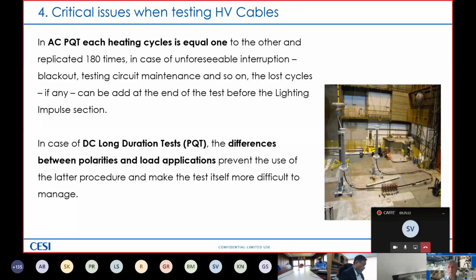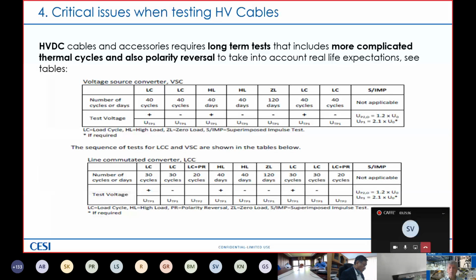Totally different situation for a long duration test in DC. Because unfortunately, here we have differences between polarities and load application. And this unfortunately prevents the use of the latter procedure, the one to put cycles at the end, and makes the test itself, of course, more difficult to manage. In fact, if you look at this taken from IEC 62895 or CIGRE Technical Brochure 490, these are the load cycling, the 180 cycles to be applied for the long duration test. In this situation, if you look at the voltage source converter or the line commutated converter, in one case, you do not reverse the current flux, in the other you have to.